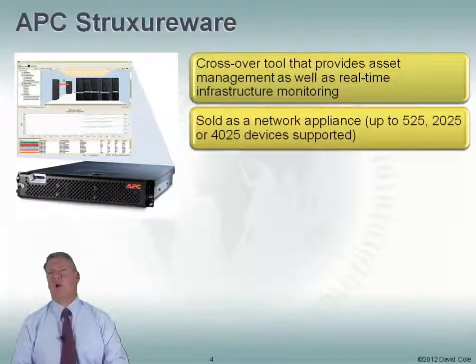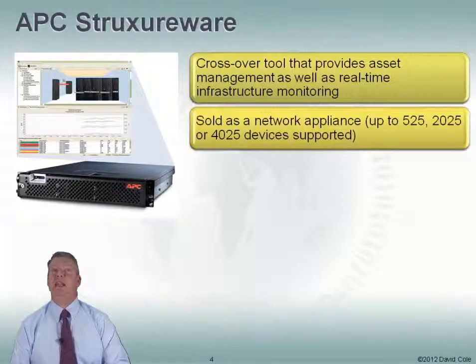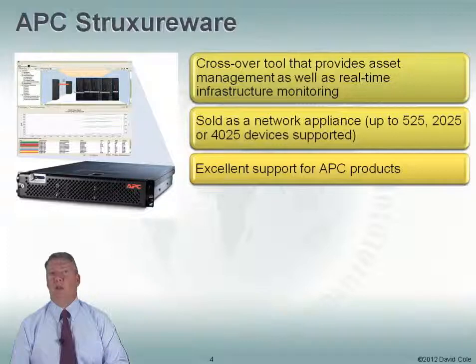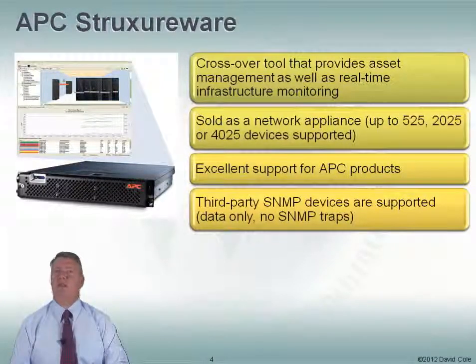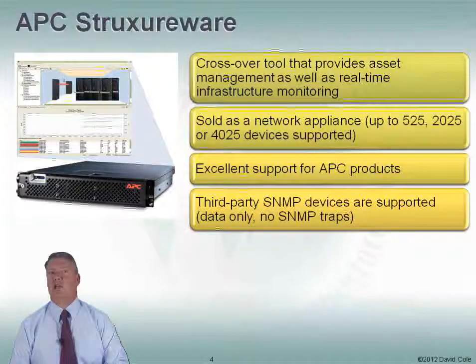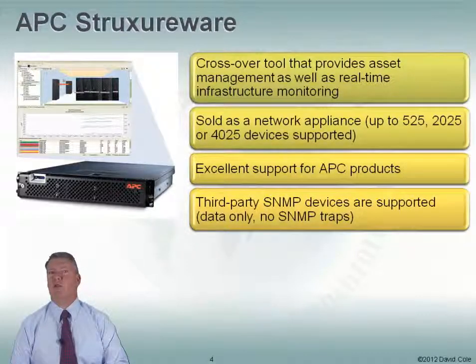They sell this as a network appliance which will support up to 525, 2025, or 4025 devices. So as you add more devices, you may need to buy more network appliances. They have really good support for APC products, but they also do a nice job of supporting third-party devices as well, particularly SNMP devices. They only support SNMP data polling — they don't support SNMP traps coming from other devices, which means you might need to poll for alarms — but they've done a really good job of working with third-party equipment.